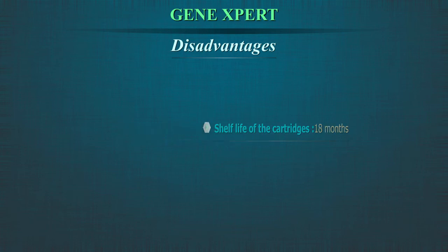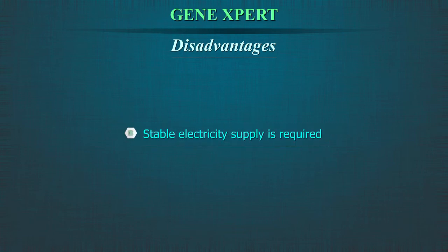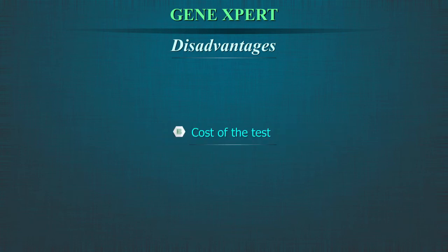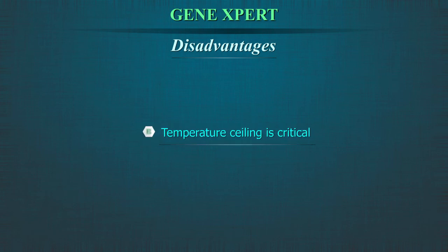There are a number of disadvantages, which include: the shelf life of the cartridges is only 18 months; a very stable electricity supply is required; the cost of the test; and temperature ceiling is critical.